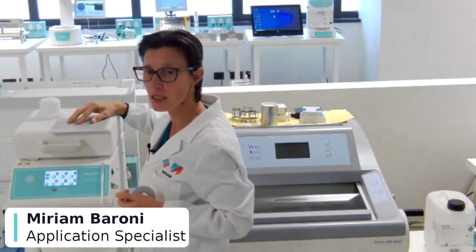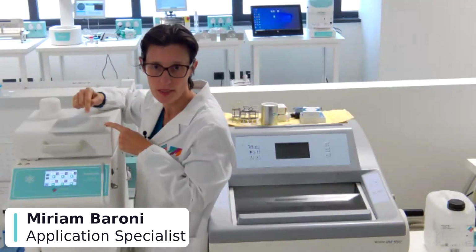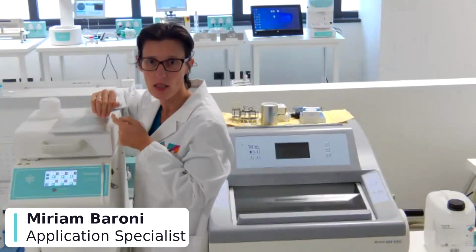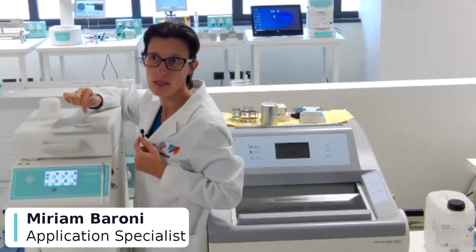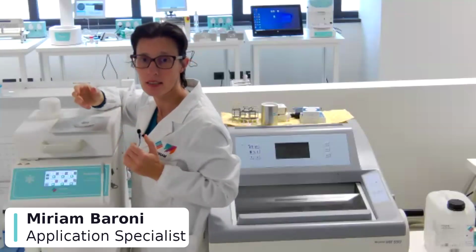The other protocol that we use is to put inside the Presto Chill a flat surface like this one. And when it is at -40 degrees, it's possible to put the Mohs sample, the skin sample, directly on it, and push down all the margin in order to have all of them at the same level. Then we use this ring to create a sort of mold and side around the sample. We fill with the medium, put the chuck, and we create the block.